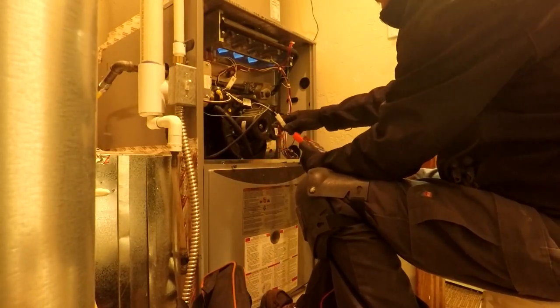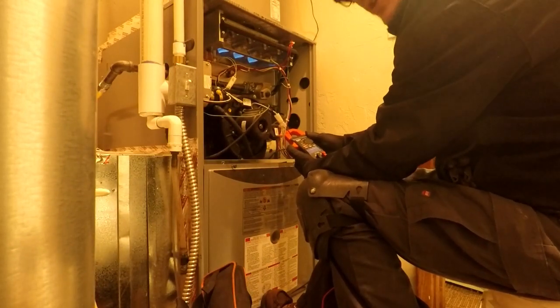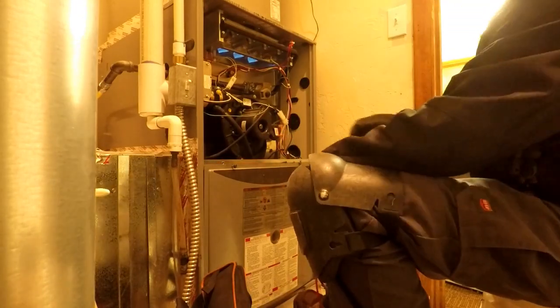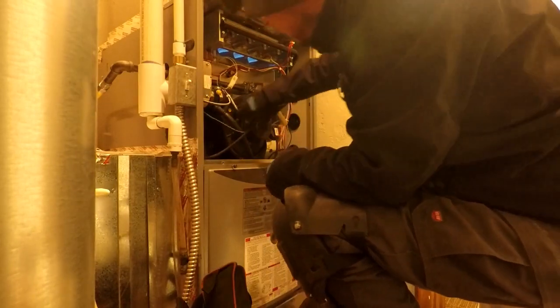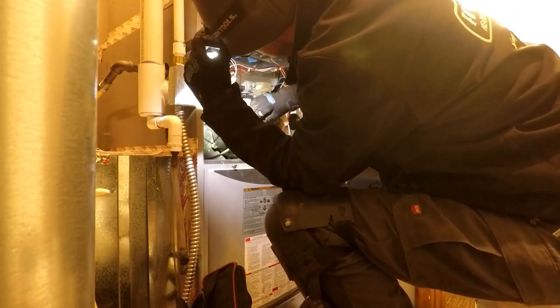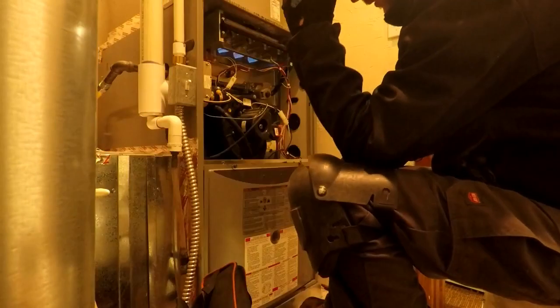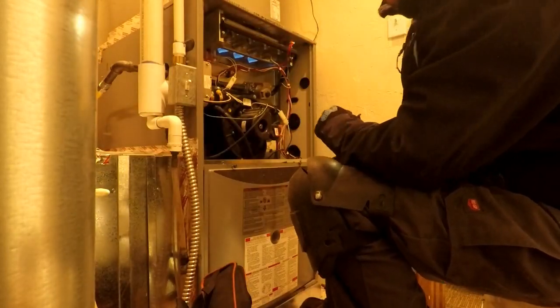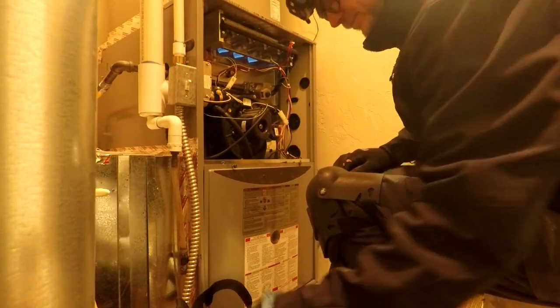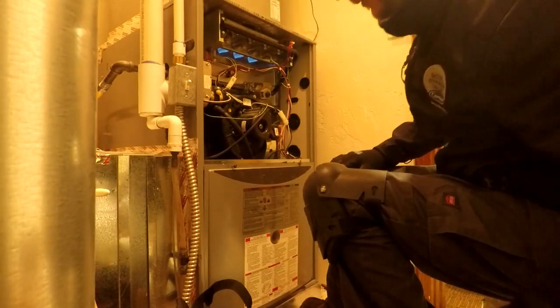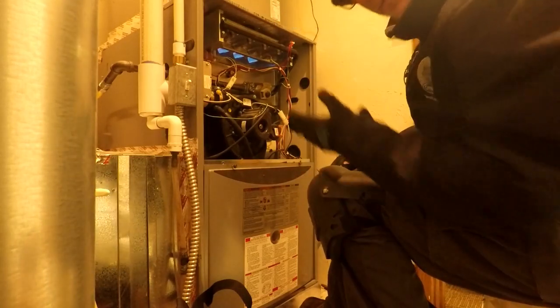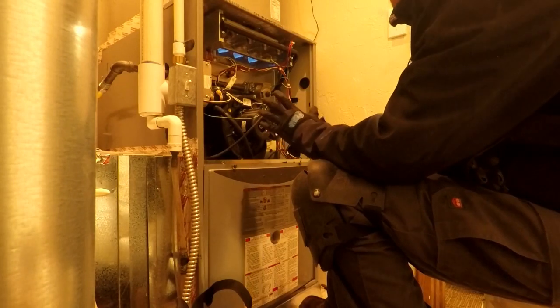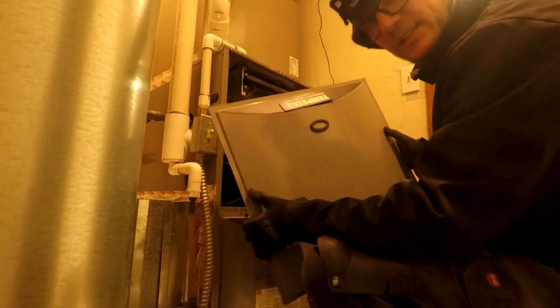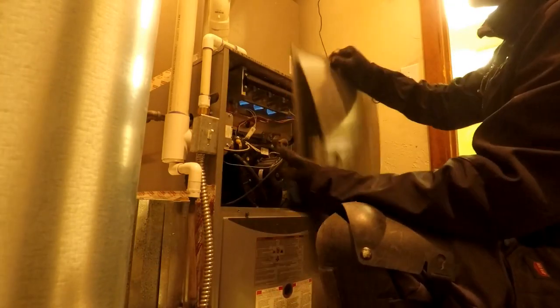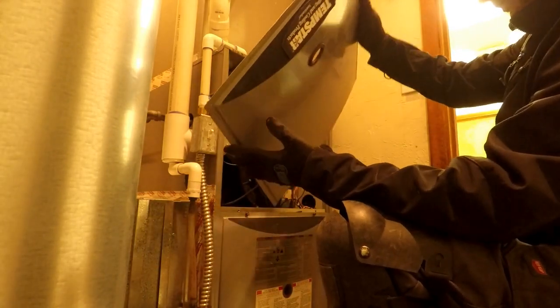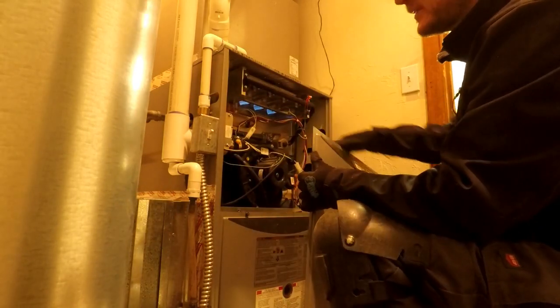3.18, 2.11, 3 on the neutral, 2 on the hot leg. The motor's rated for 2.4 amps, so it's not like crazy overamping, maybe a little bit on that neutral leg, but I've seen them do that many times and it never caused an issue. So I'm going to slap the cover back on it and see if that changes anything with the way that flame reacts.